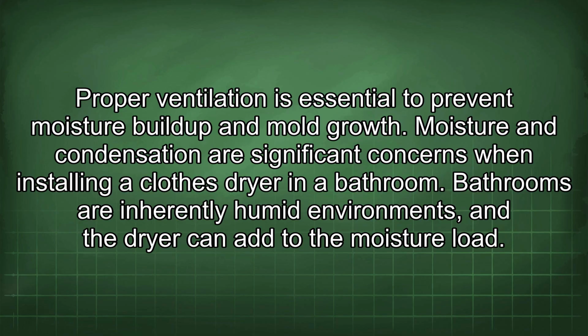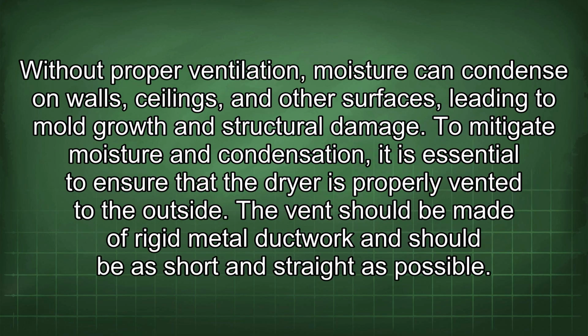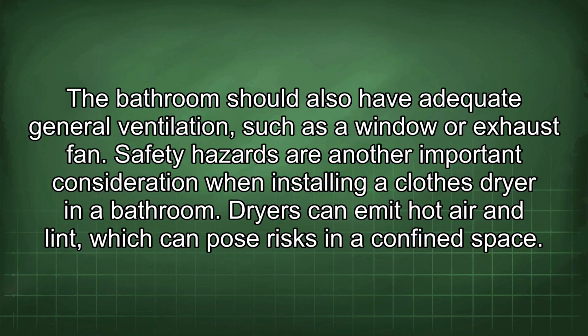Moisture and condensation are significant concerns when installing a clothes dryer in a bathroom. Bathrooms are inherently humid environments, and the dryer can add to the moisture load. Without proper ventilation, moisture can condense on walls, ceilings, and other surfaces, leading to mold growth and structural damage. To mitigate moisture and condensation, it is essential to ensure that the dryer is properly vented to the outside. The vent should be made of rigid metal ductwork and should be as short and straight as possible. The bathroom should also have adequate general ventilation, such as a window or exhaust fan.